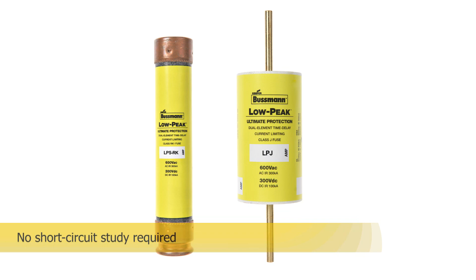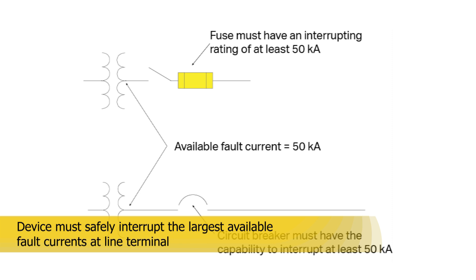Nor is a short circuit study needed when applying Bussmann series dual element time delay low peak fuses for selective coordination, so meeting NEC requirements is easy. Additionally, high interrupting ratings help equipment achieve a high short circuit current rating that may be limited by a device with a low interrupting rating. When applying a fuse or a circuit breaker, the device must be able to safely interrupt the largest available fault currents at its line terminals.